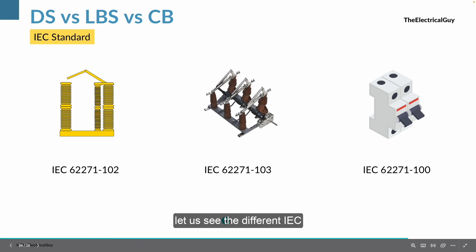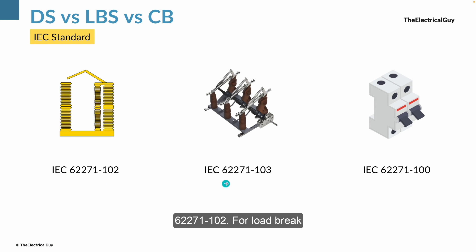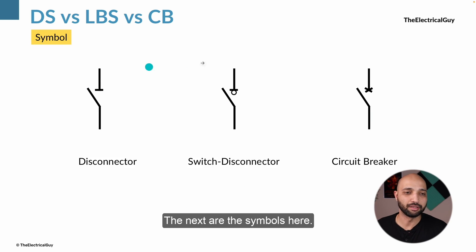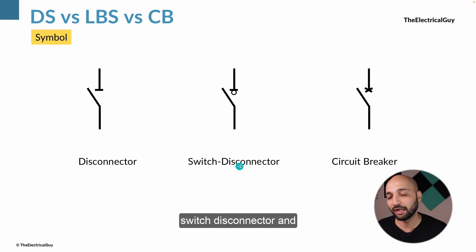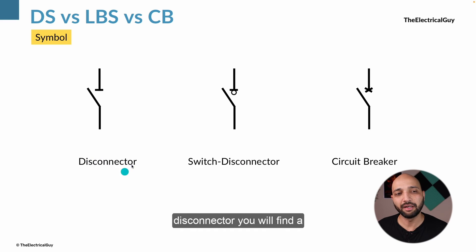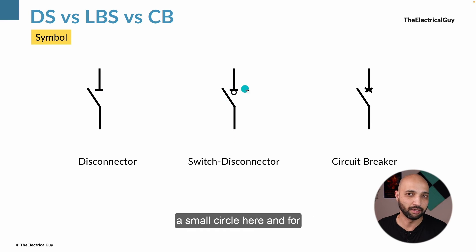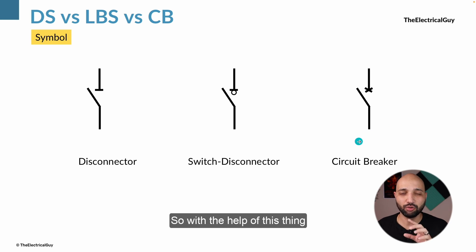Looking at the IEC standards: for disconnector it is IEC 62271-102, for load break switch or switch disconnector it is 103, and for circuit breaker it is 100. Regarding symbols: for disconnector there is a horizontal line; for switch disconnector there is a horizontal line with a small circle; and for circuit breaker there is a cross mark. These visual cues help you remember the symbols for each device.